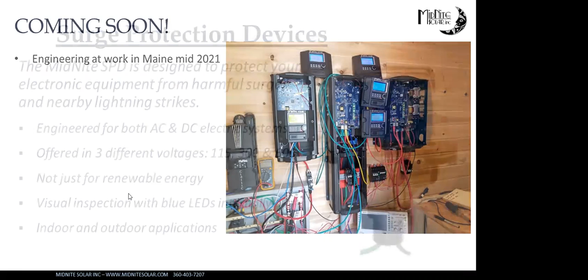I don't know how many here are familiar with our surge protection devices, but they're very cheap insurance. They work well, very robust. Of course there's no guarantee against lightning, but you can try to do your best. We've had some that actually got hit by lightning and saved equipment. We've had some equipment fail when hit by lightning too - if it's a direct hit, all bets are off. But I'd venture a guess that 80 to 90% of the damage caused by lightning is not a direct hit - it's induced voltage from a nearby strike, and in that case they're going to work great.